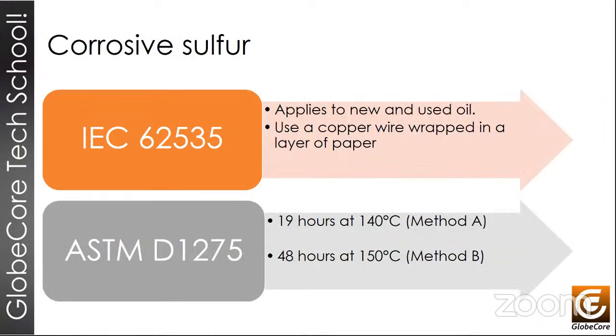Next, please. Okay, there's another problem that also requires the addition of an inhibitor, or actually a passivator, and that is corrosive sulfur. Corrosive sulfur will damage the insulating paper and copper windings of the transformer, and it's an issue that increasingly affects power transformers now. There are several tests that are carried out in oil to determine the sulfur content inside the transformer. There is IEC 62535 test. It's used to find the copper sulfide residues in transformer paper, known as CCD. ASTM D1275 test is used to determine the effect of sulfur on copper strips.